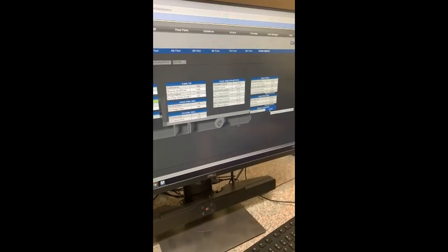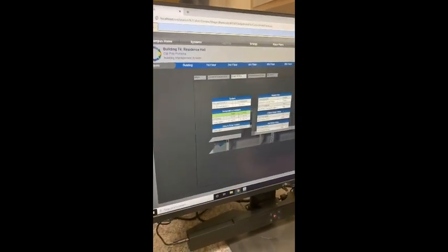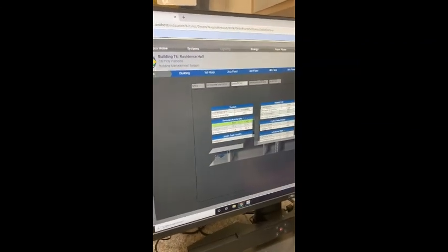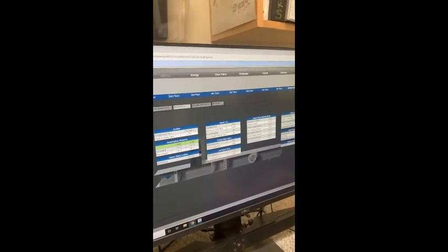Right now we're having an issue with the JACEs with the global set points and the load. But it's all there for it to work, and once we have a solution, it will work. When we go into the dorm FCUs and try to do something in there, does that modify the coordinator apartments and stuff like that?